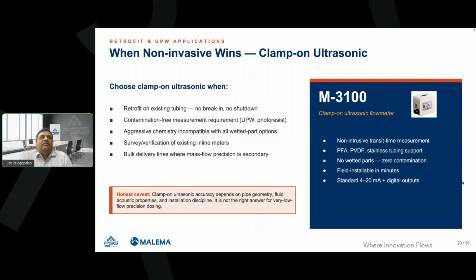The other product that wins in this application is the clamp-on ultrasonic flow meter. The advantage of clamp-on ultrasonic flow meters is that they are fitted externally to the tubing, so you're not breaking the tubing, so there are no leak points, no obstructions, and no need to shut down if you're retrofitting older tools with newer technologies such as clamp-ons. It's completely contamination free. Only the tube is of concern here, aggressive chemistries can be used, and for bulk delivery lines where the mass flow precision is secondary, you can use the clamp-ons.